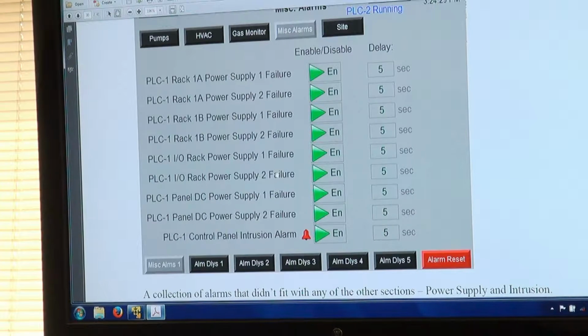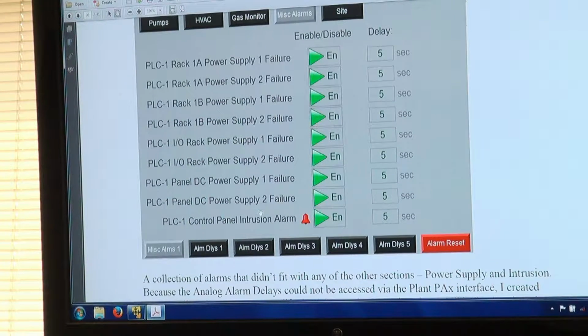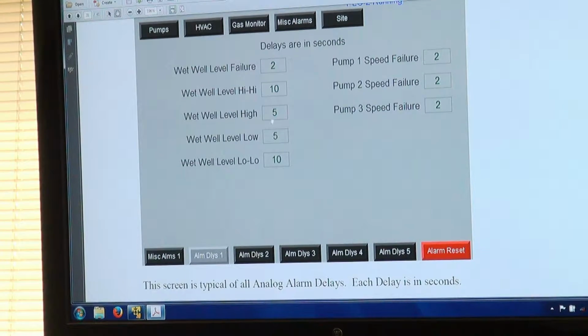Your I/O rack, if you did lose both power supplies, then you do have a problem because you can't go in or out. So all your VFDs would be off, all your statuses would be off, you wouldn't look at any levels. That would be a major fault. We do have DC power. We use that for reference for a lot of things, and also controlling equipment, usually comm equipment within there. Finally, we have our intrusion alarm, and as you can see, we actually have an intrusion right now because that's what that little alarm bell is. Your alarm delays, these are all in seconds.